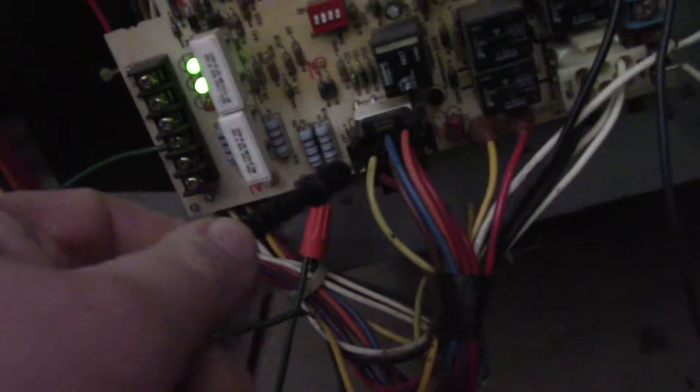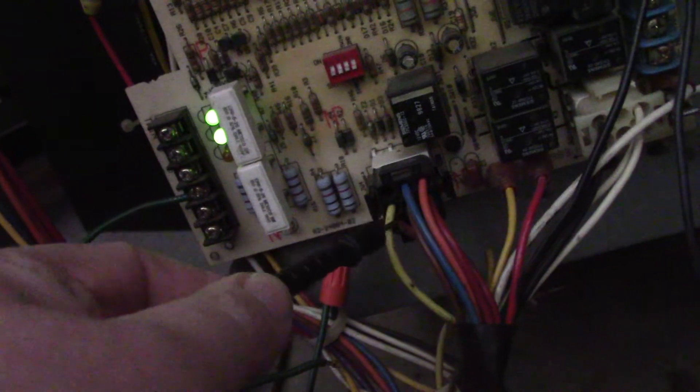You follow it down through here, see what plug you have, disconnect here, you can ohm out there or if the wire connections are here you can disconnect it and ohm out there. Remove that plug, put your meter probes in there and you can ohm out the secondary side. So if your transformer says 10 ohms primary, OL on secondary, congratulations the secondary side of the transformer has been fried.